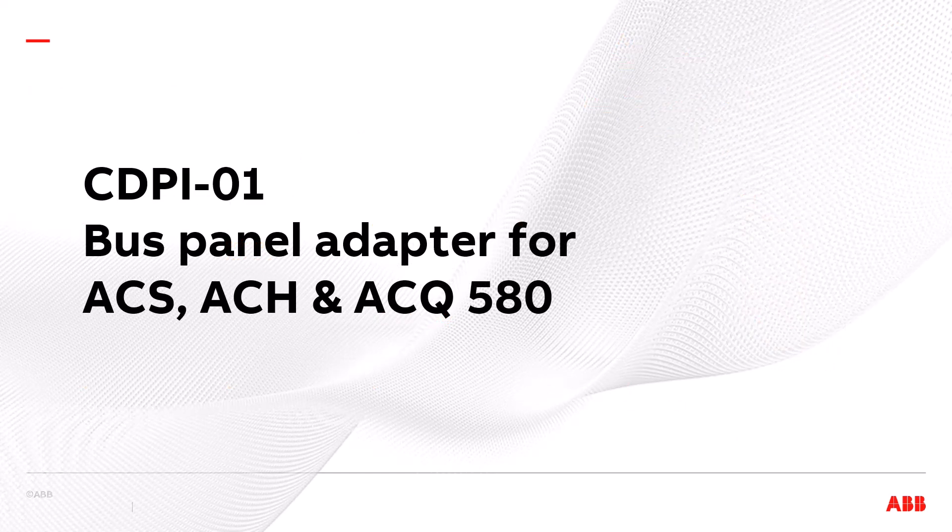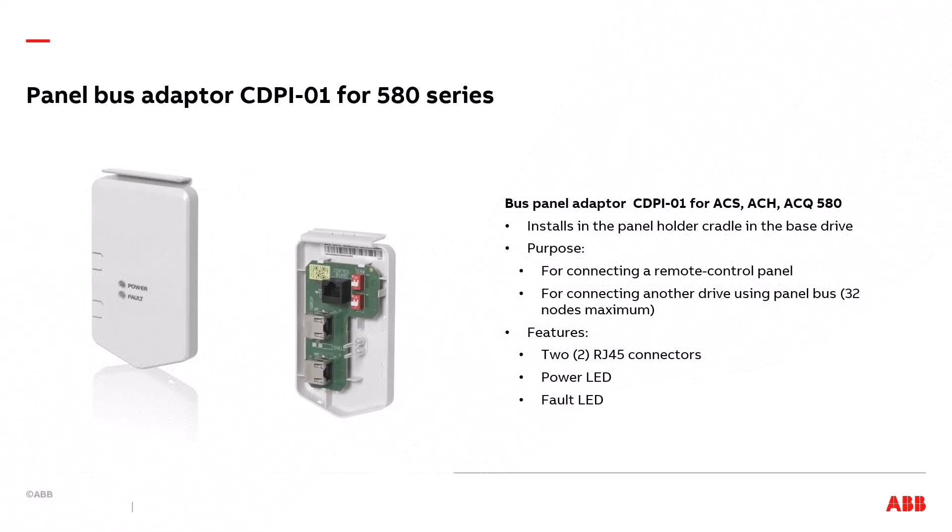CDPI-01 bus panel adapter for ACS, ACH, and ACQ 580 drives. In this presentation we've talked a few times about the CDPI-01 panel bus adapter for the 580 drives. This is what looks like a dummy control panel that gets installed in the normal place of the control panel on the front of the base drive. Its purpose is to allow a remote control panel to connect to the 580 drive. It is also used for connecting multiple drives together using panel bus. It features two RJ45 connectors, a power LED, and a fault LED. It is only used on the 580 drives.